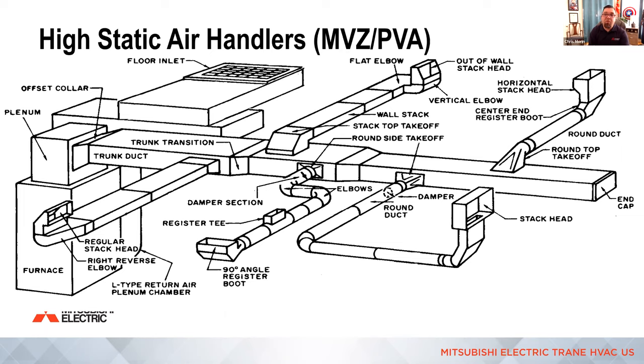Each one of these fittings has a different equivalent length value. And remember, just because it's the furthest away on the supply does not make it the longest run. The longest run is in equivalent length values. Sometimes in this example, you can see the second longest might have, it says a stack head, but that stack might go up to the second or third floor. And that is further away and more equivalent length with all of the turns, okay? So typically you're looking at the one or two or three furthest away to determine which one has the worst fittings to know which one's the longest run, all right? And always a top takeoff is a much higher value than a side takeoff. It's usually 40 or 50 feet for a top takeoff. And the max on a side takeoff is 35 feet. So usually any side takeoffs that are further away is your longest run.